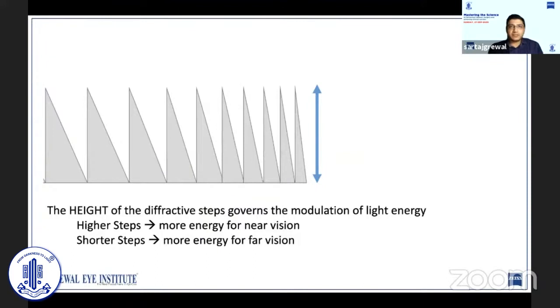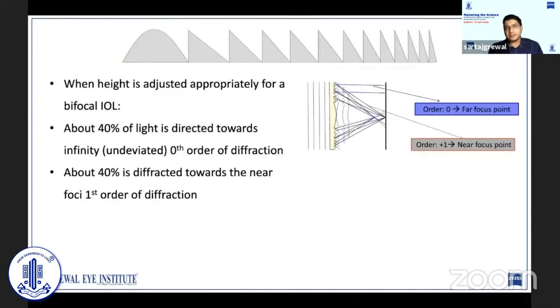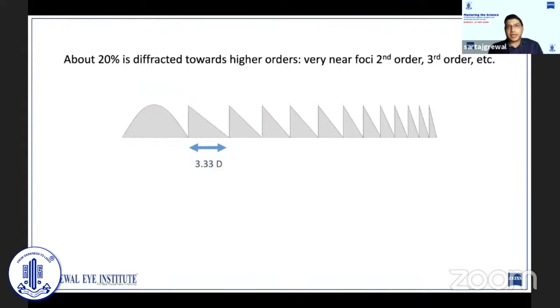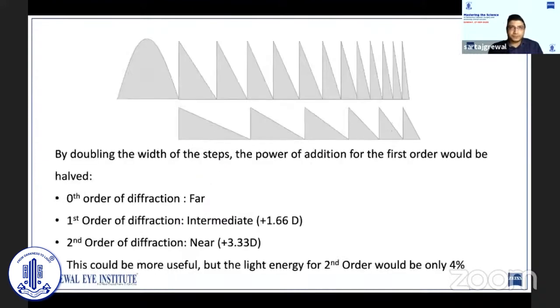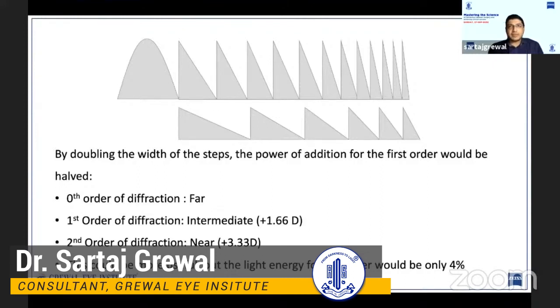The height of the diffractive steps governs the modulation of light energy and essentially the orders of diffraction produced. Most bifocal IOLs distribute light such that 40% is directed towards infinity, 40% for near vision, and the remaining 20% is directed towards higher orders. It is this 20% of light going towards higher orders of diffraction that is responsible for photic phenomena such as glare and halo experienced with these lenses. Since the second order diffraction would result in a near add of over six diopters, it would be too high to be clinically useful. By doubling the width of the steps, the power of addition for the first and second order could be halved, resulting in first and second order adds of 1.66 and 3.33 diopters respectively, which would be very useful clinically for patients.